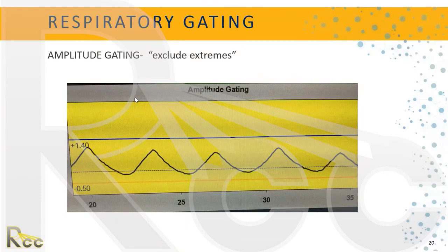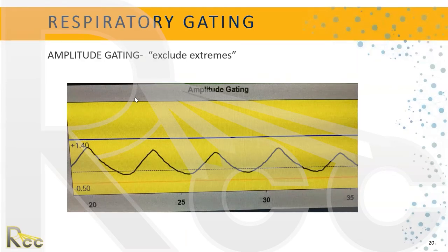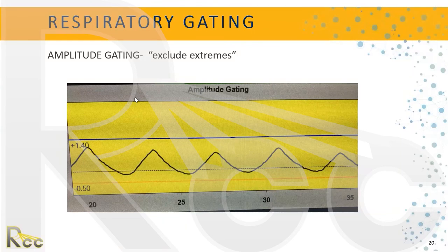Q&A on improvised gating: Without gating equipment, you can do what's called 'poor man's gating' — coaching the patient to take a really deep breath in and hold it, or to breathe all the way out and hold it, while you scan. For simulation, you need a fast scanner to capture the patient before they need another breath. For treatment, you need a short enough treatment segment that the patient can hold their breath for the entire duration on your instruction.